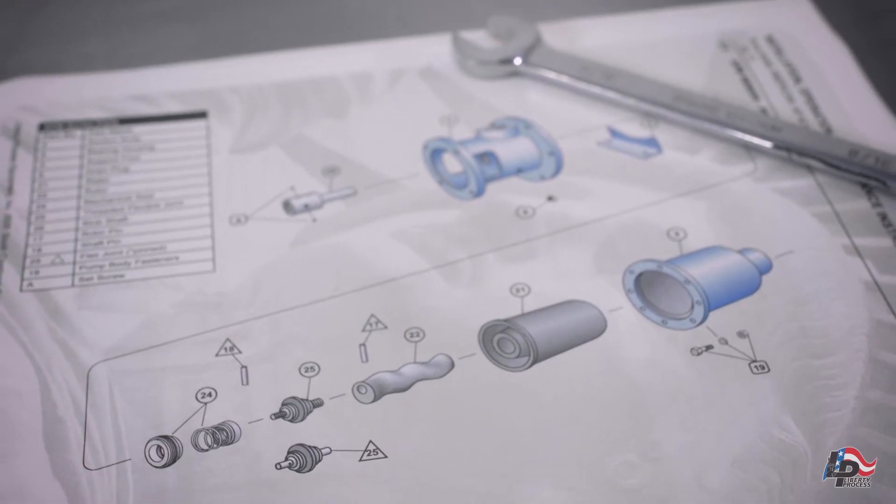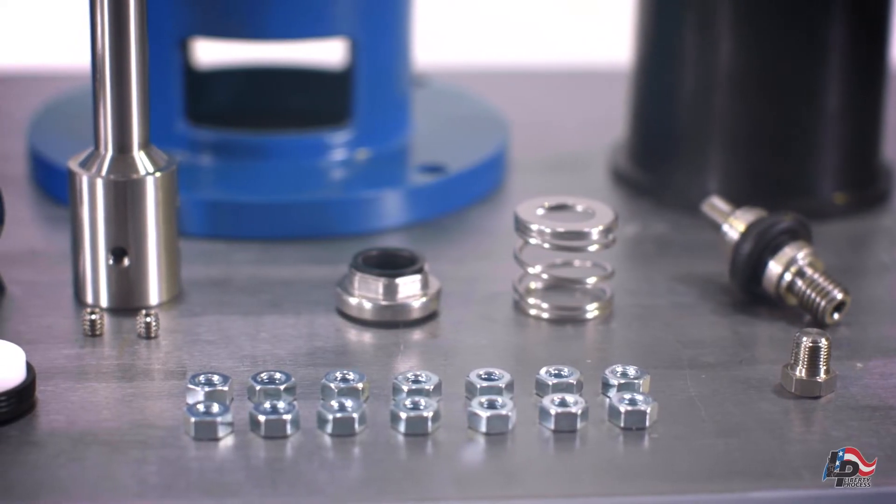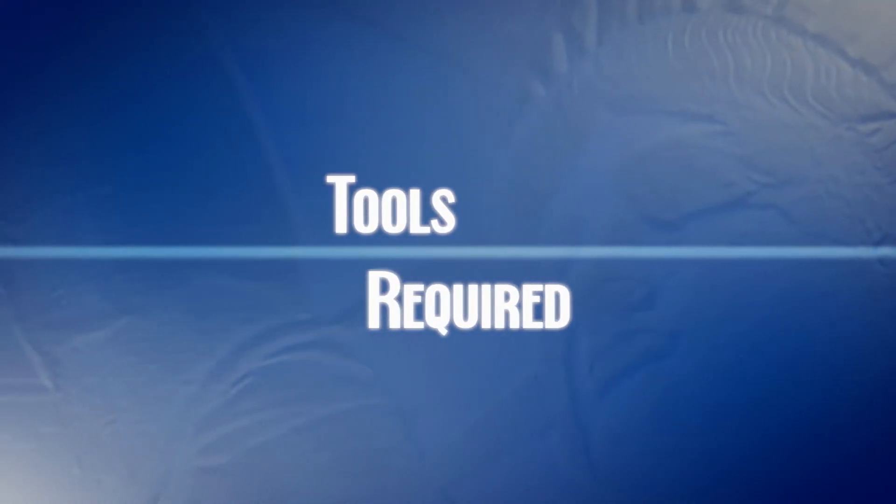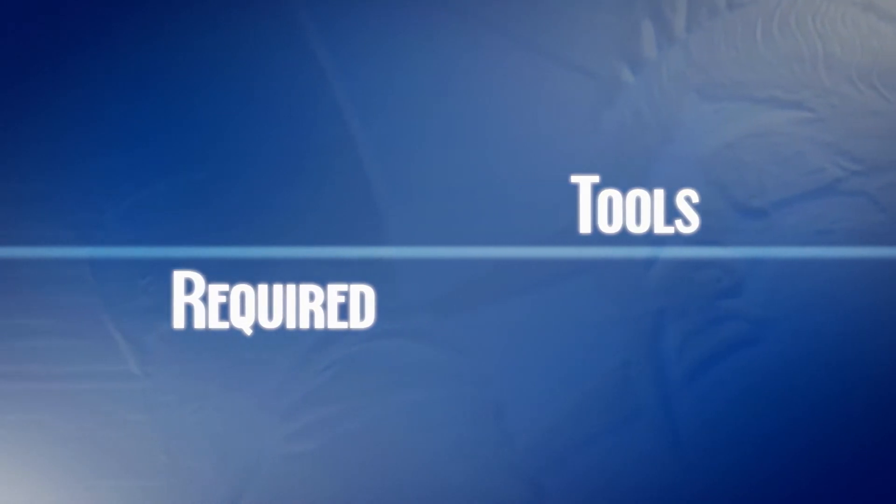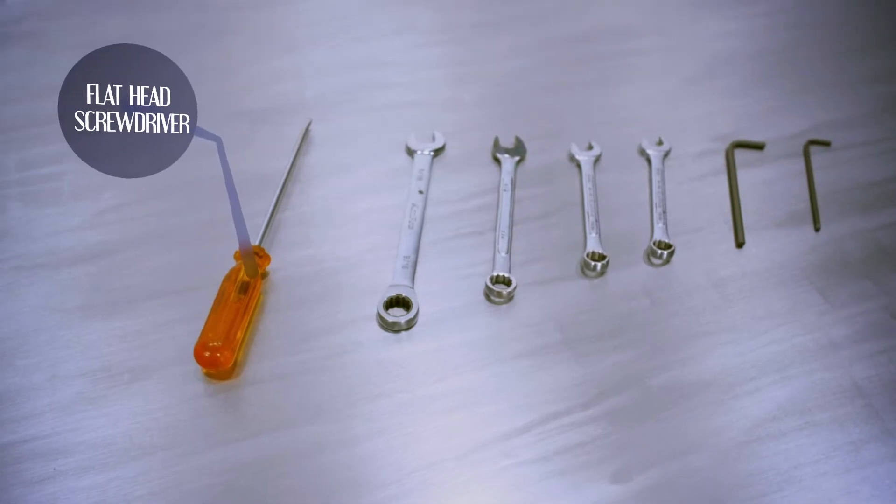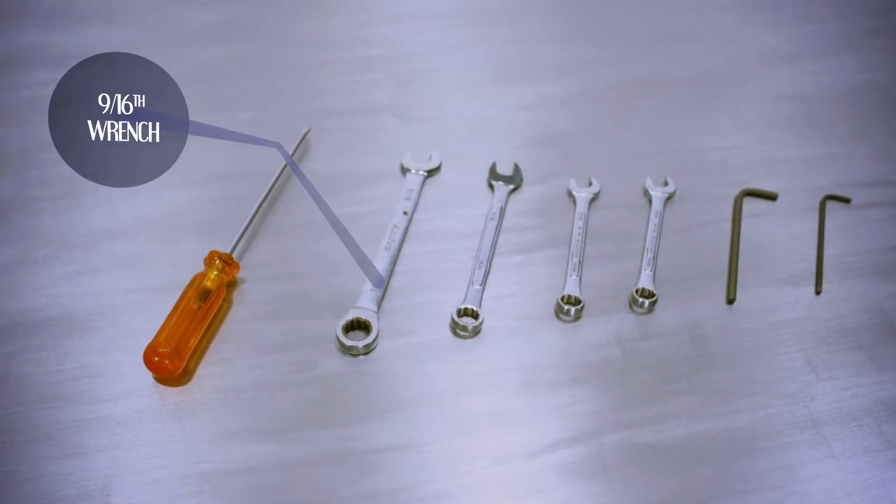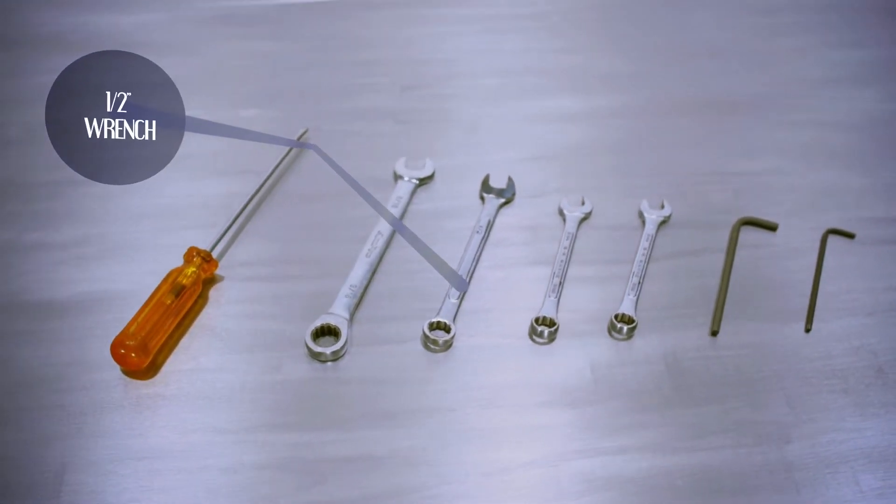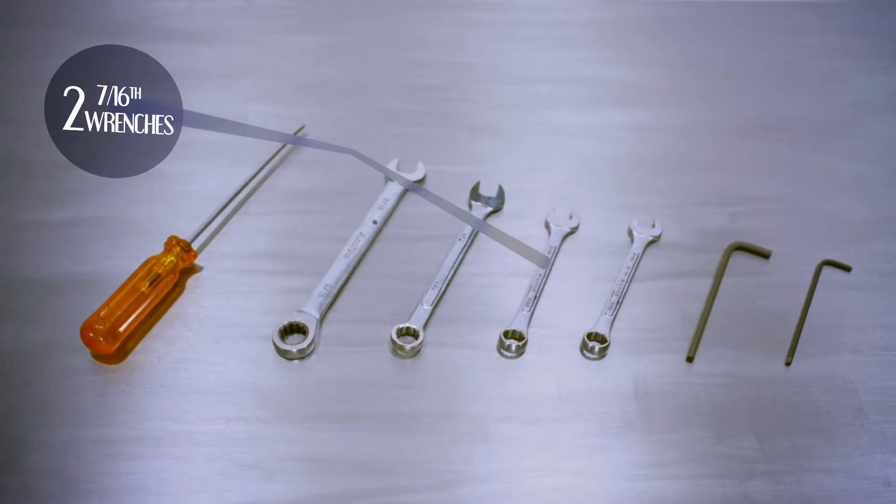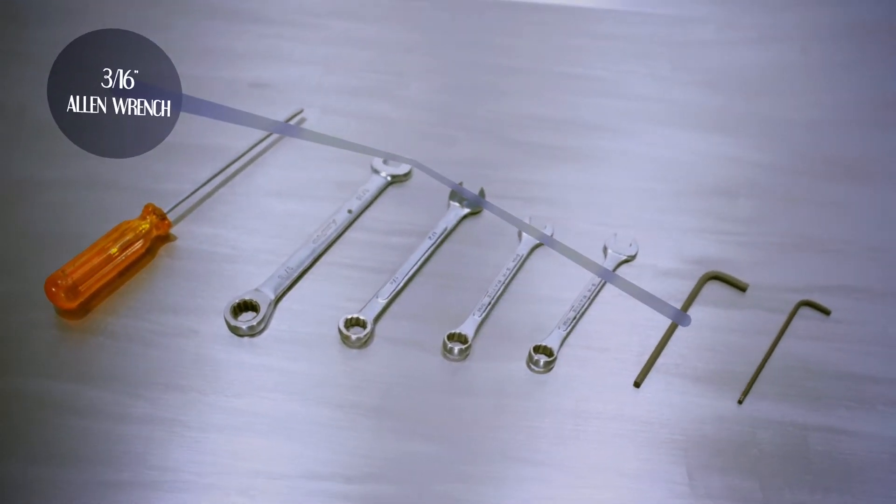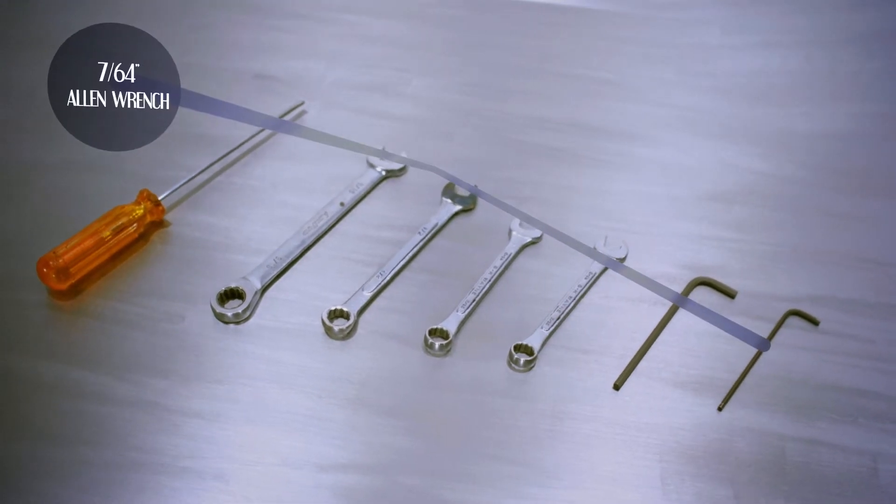Before we begin, if the pump has been used, we recommend that you have flushed and drained the pump of all pump mediums and have a clean repair surface on which to work. Tools required for the APM 22 pump disassembly: a flathead screwdriver, a 9-16-inch wrench for pump motor mounting bolts, a half-inch wrench for the drain plug, two 7-16-inch wrenches for the pump casing bolts, a 3-16-inch Allen wrench for flex joint removal, and a 7-64-inch Allen wrench for stub shaft set screws.